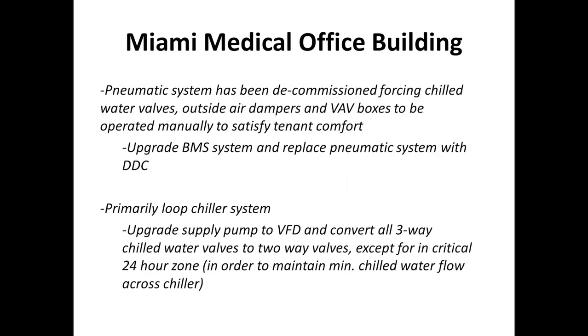But essentially, the major issue in this building was that there was an outdated pneumatic system that had been decommissioned. So the VAV boxes, air handling units, and also outside air dampers and chilled water valves were all operated off pneumatics that had been disabled. In order to meet comfort conditions in the space, the building manager had to run around and adjust VAV dampers, chilled water valves, and outside air dampers completely manually, either by wedging cardboard or a stick to hold the position of a valve or a damper. And a lot of heat and humidity was getting into the building that shouldn't have been.